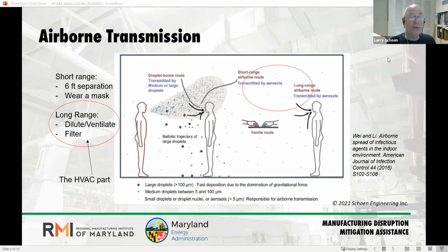But on the longer range, particularly when people are in the same room, we do not want to have tightly enclosed spaces with bad air filtration. So therefore, we say it in the positive, dilute air with outdoor air. That is, by the way, presumed not to be heavily contaminated. Even though people are using the term shelter in place, this is not a shelter in place situation. Shelter in place is when you have an air contaminant outside. We want to expose our indoor spaces as much as possible to the outdoors because those are presumed to be cleaner. So that's the HVAC part.